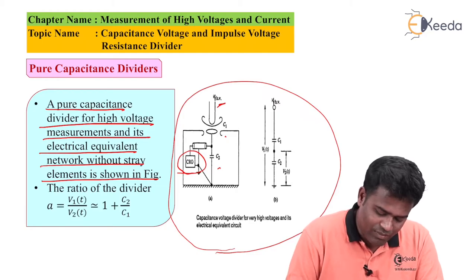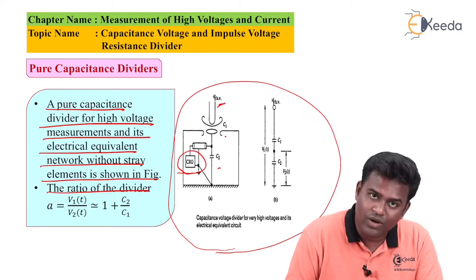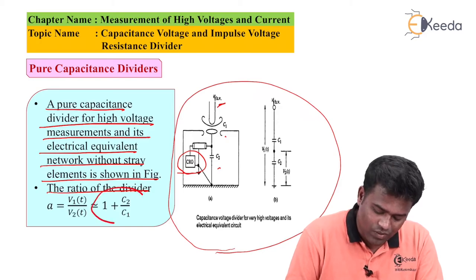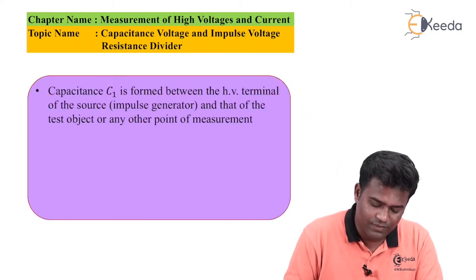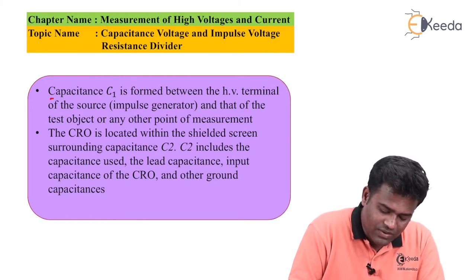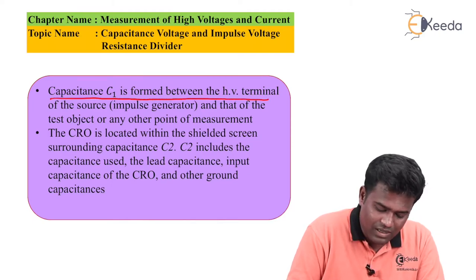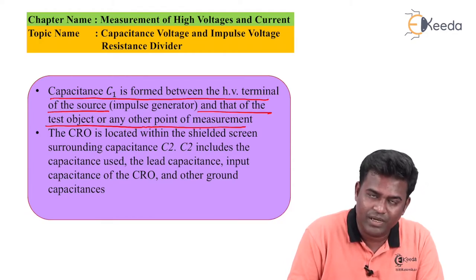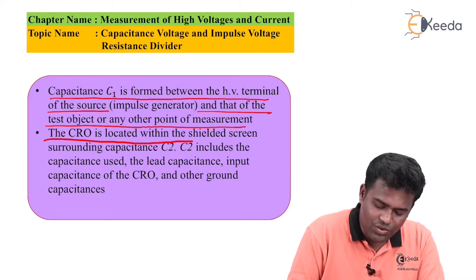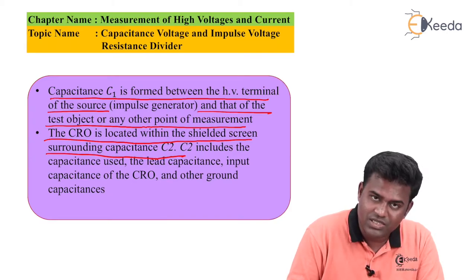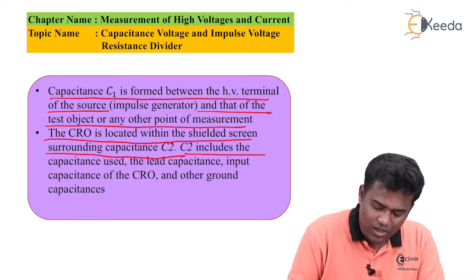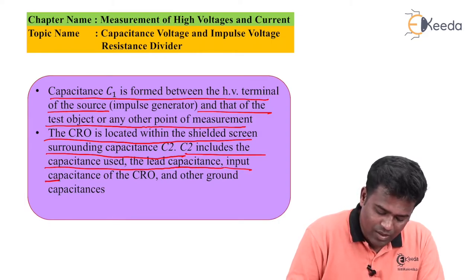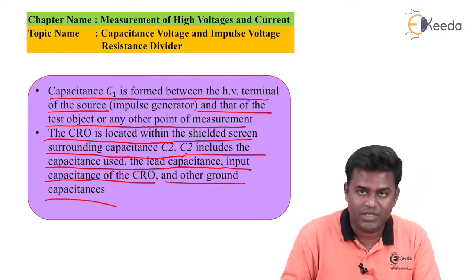The output form, which is independent of frequency, can be obtained on the CRO. The ratio can be given as alpha = V1(t)/V2(t) = 1 + C2/C1. Capacitance C1 is formed between the HV terminal of the source and that of the test object or any other point of measurement. The CRO is located within the shielded screen surrounding capacitance C2. C2 includes the capacitance used, the lead capacitance, input capacitance of the CRO, and other ground capacitances.